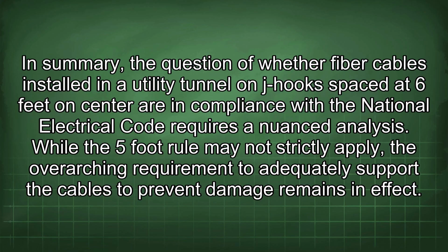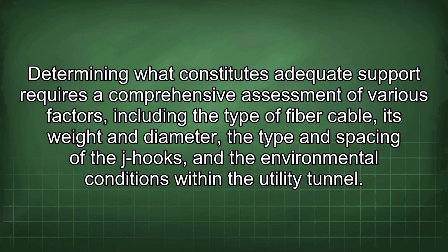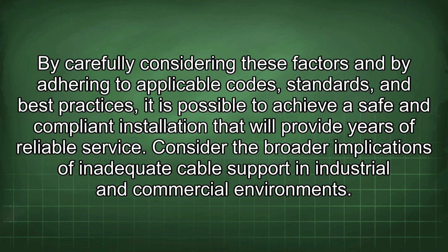While the 5-foot rule may not strictly apply, the overarching requirement to adequately support the cables to prevent damage remains in effect. Determining what constitutes adequate support requires a comprehensive assessment of various factors, including the type of fiber cable, its weight and diameter, the type and spacing of the J-hooks, and the environmental conditions within the utility tunnel. By carefully considering these factors and by adhering to applicable codes, standards, and best practices, it is possible to achieve a safe and compliant installation that will provide years of reliable service.